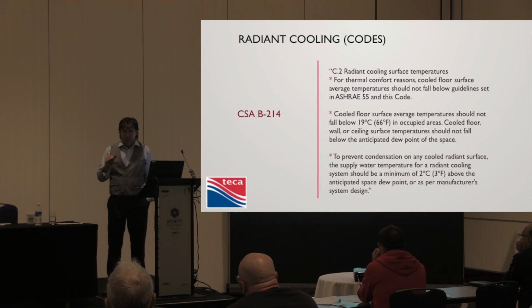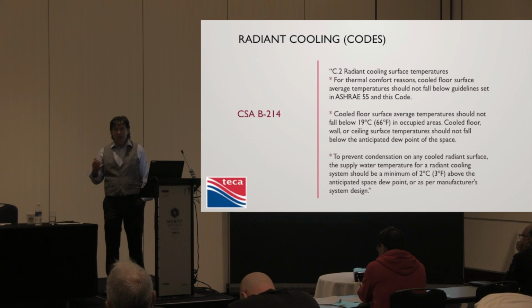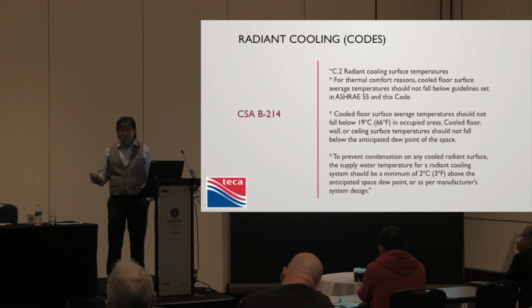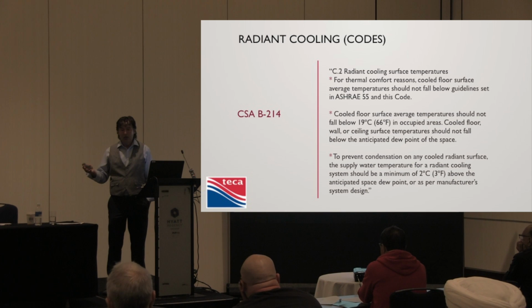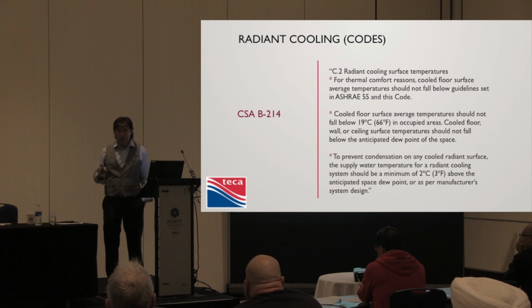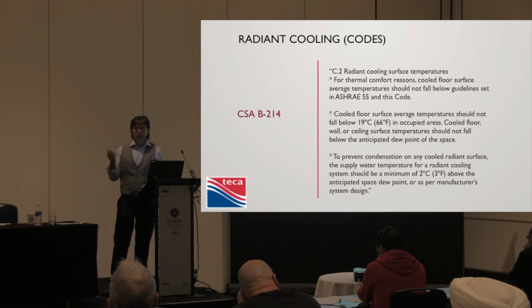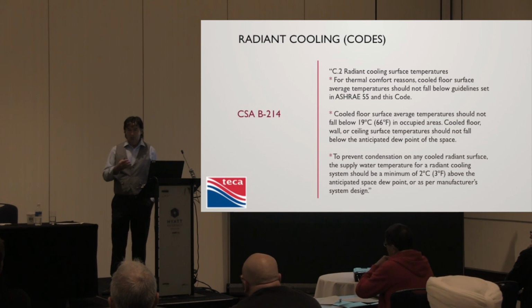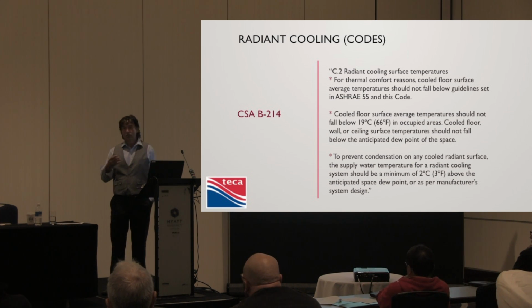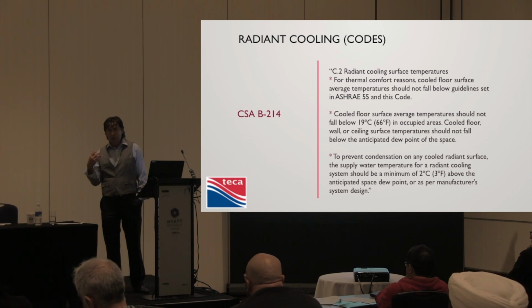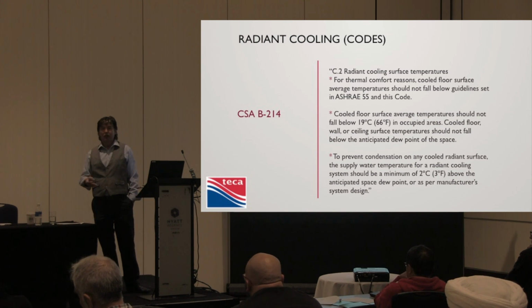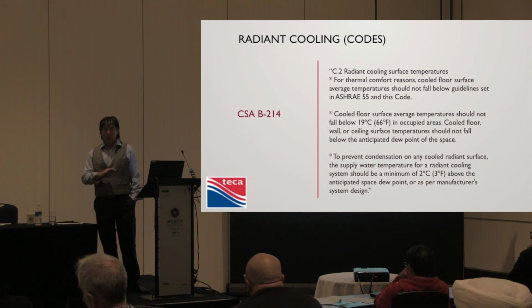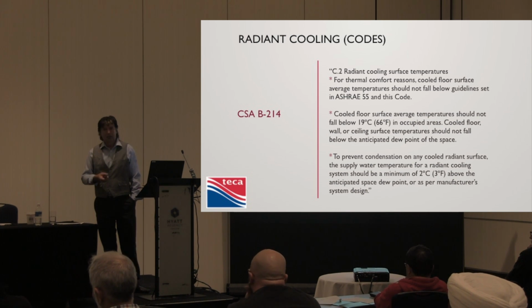So the biggest negative is we're not dealing with the latent load. Radiant cooling is dealing with only the sensible load. It's not dealing with the moisture and the mugginess in the air. And on output, we can get a lot more cooling capacity out of moving air than we can out of a radiant surface for cooling. Now certainly you can put cooling into air using hydronics, heat pumps, air to water heat pumps going into a fan coil. You're cooling water, but really in that case you're cooling air, and now you're dealing with the latent load, etc. But as far as radiant cooling goes, those are the negatives.